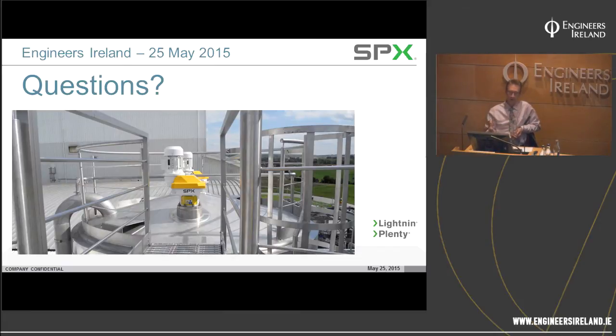But it's interesting talking about the main flow impinging on the impeller and bending the shaft, because that's something we do try to avoid. It's normally coming in at the side. So in something like a flash mixer or a neutralization tank, you've normally got the flow coming in from the side and going out the other side. Hopefully in this case the recirculation is higher than the flows, and they probably do something daft like running the impeller at the liquid level as well. That doesn't help. No, certainly, it doesn't help unless you've designed for it.